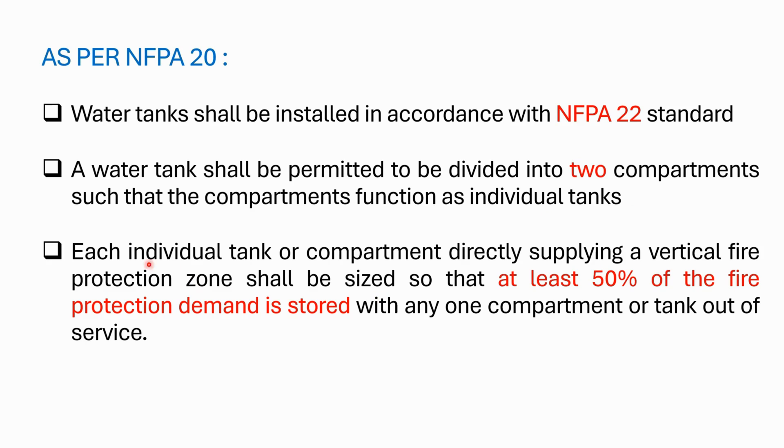The third point would be each individual tank or compartment directly supplying a vertical fire protection zone shall be sized so that at least 50% of the fire protection demand is stored with any one compartment or tank out of service. I will explain you a little bit.